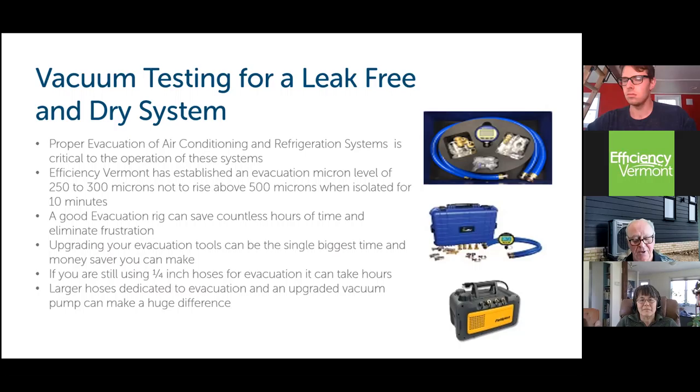Now, I want to mention something about those core removal tools. The really good ones that I would recommend would be something like an Appion tool. They're really made for leak testing as much as evacuating. They're really tough tools.